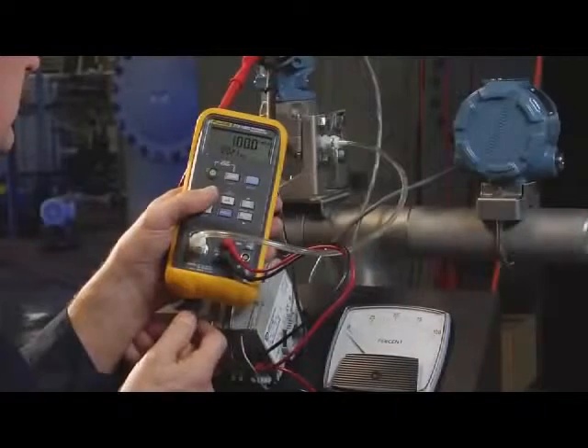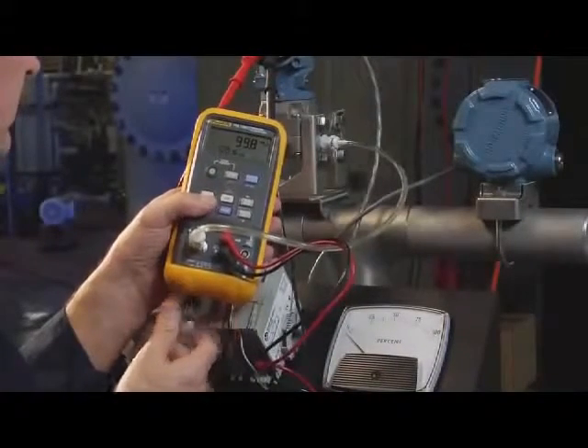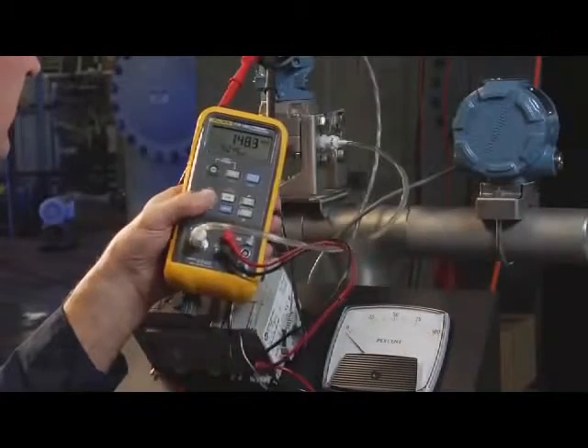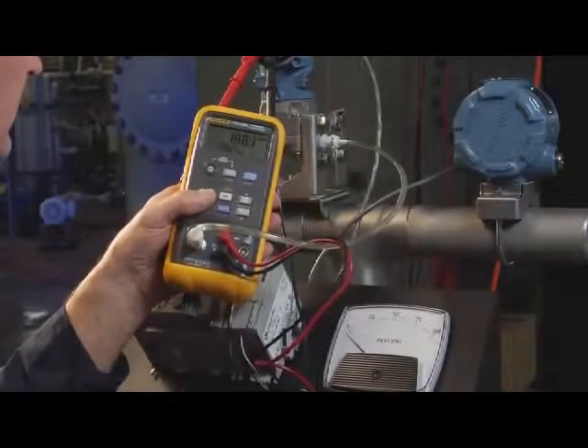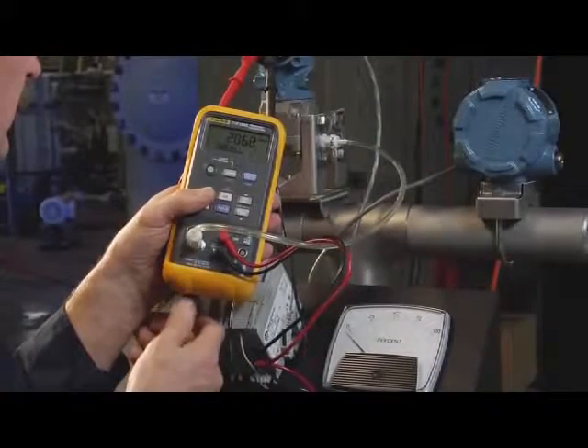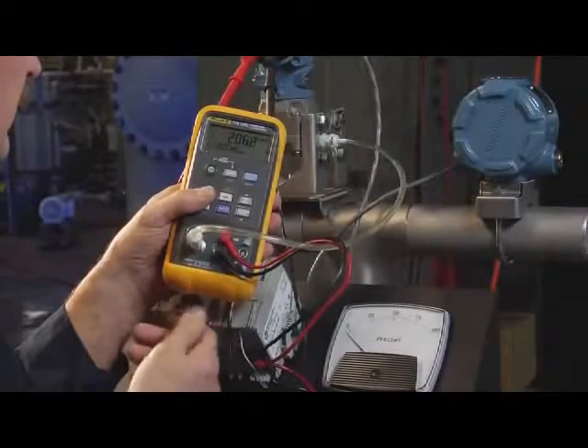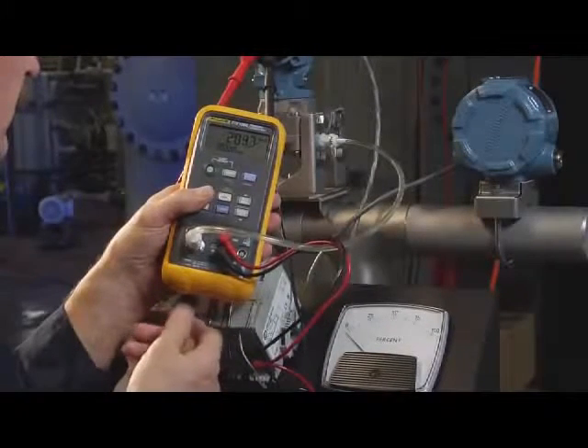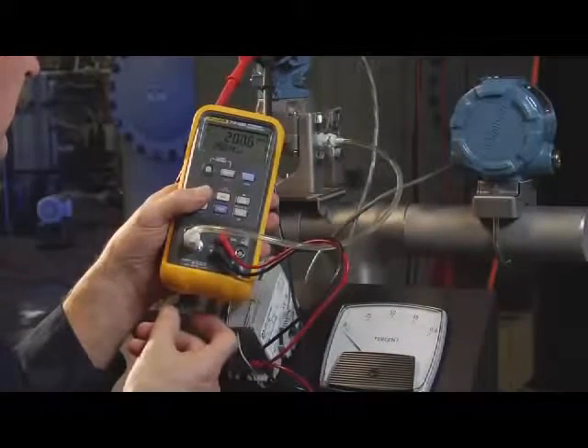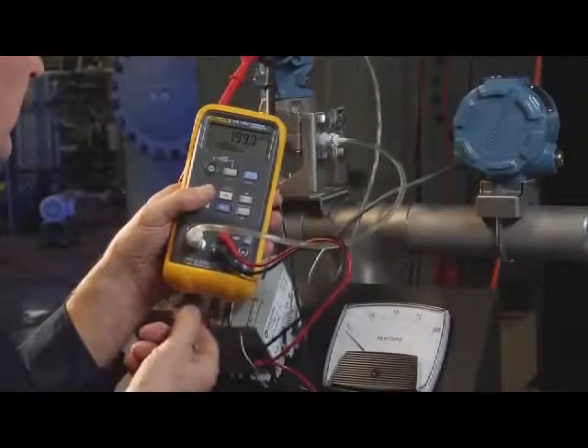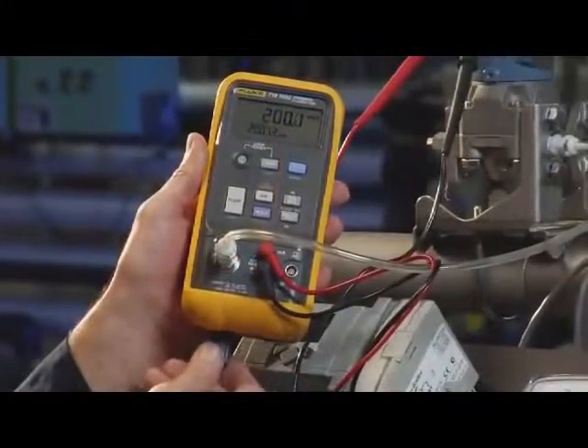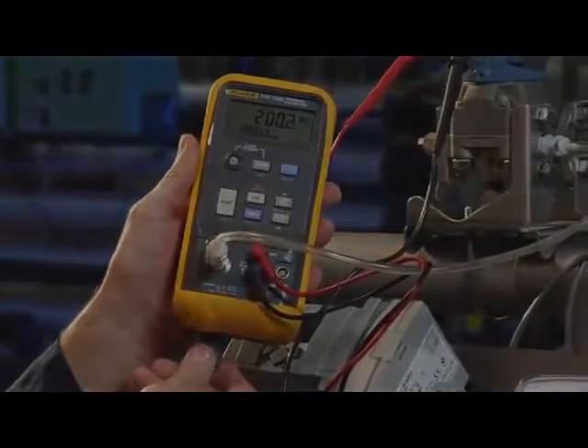The last step is to test the full-scale pressure value of the transmitter, 200 inches of water. Use the electric pump to generate 200 inches of pressure. Use the fine adjust in the pump to dial in the value to exactly 200 inches and verify for 20 milliamps. With 200 inches of water applied, the deviation between measured milliamp value and 20 milliamps is the calibration error of the transmitter.